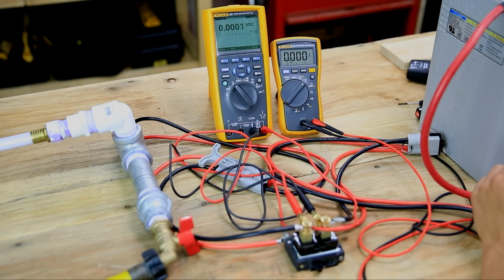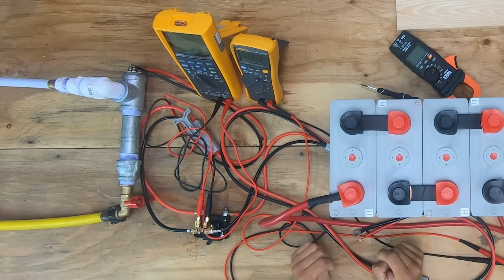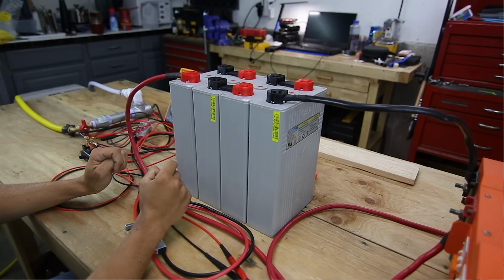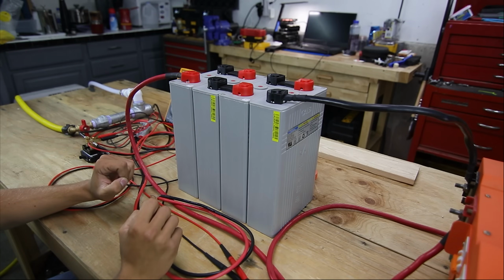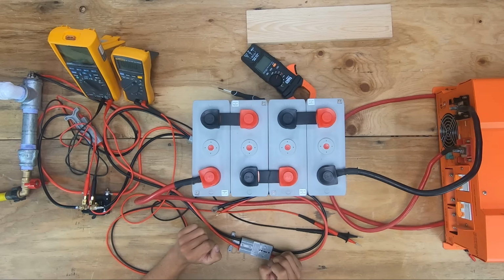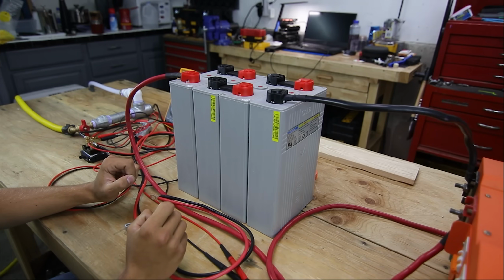I have a 600 watt 12 volt DC heating element here, cooled by running water through it, and that's the load I'm going to send the power into. I'm not going to use an inverter because it can introduce an AC harmonic into the test, and the batteries will react to that in a way that can skew the result. That's why I'm using a DC load.